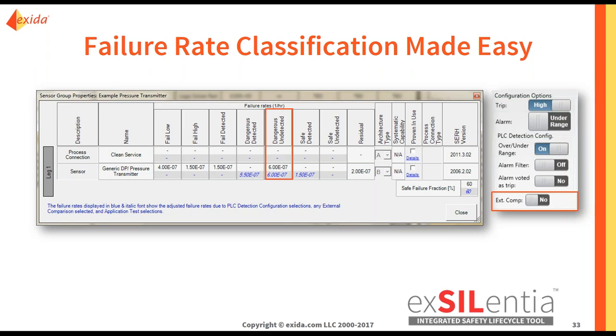Finally, you have your dangerous undetected failures, which, because we have no external comparison, are simply classified as dangerous undetected. However, these could be switched to the dangerous detected section if you have external comparison. So this is just one example of how these failure rates can be classified. If you have exSILentia, you can go in and choose different configurations and see how the failure rates are applied. If you want any help with this, you can certainly email me and we can do it together in a web meeting or in person to see how the different configurations will classify those failure rates.